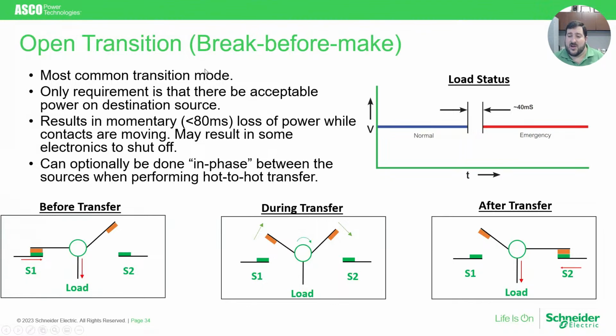As I mentioned, a transfer is something that is very often generalized, but there are many different types of transfers. The first and most common is an open transition transfer, which is a break before make type transfer, where both sets of contacts are usually connected to a single shaft. And as the shaft opens from one source and the contacts open from one source, they are simultaneously connecting on another source. On the way to transfer from source 1 to source 2, for example, in a hot-to-hot transfer scenario, that does resolve in a very short transient between 40 to 80 milliseconds, depending on the size of your transfer switch.